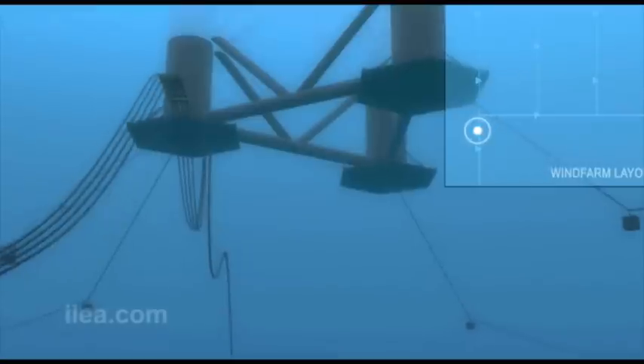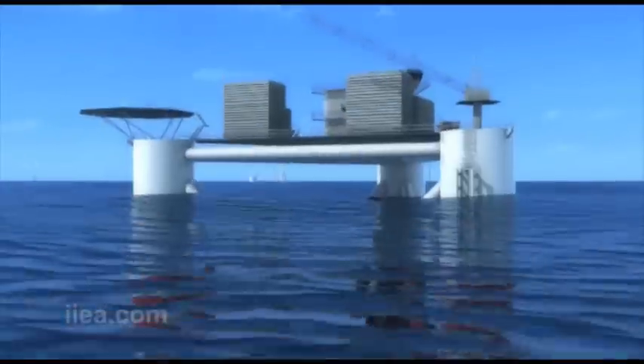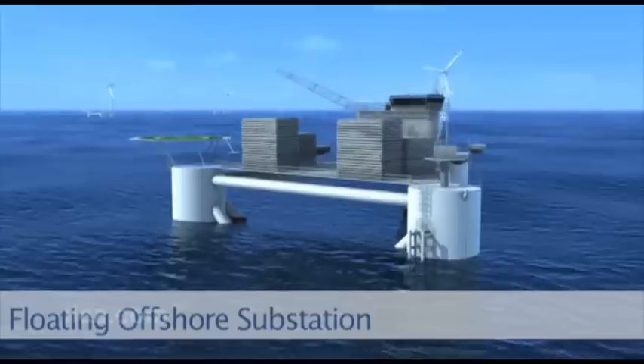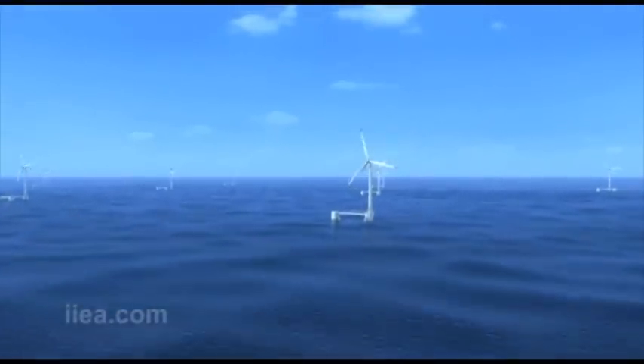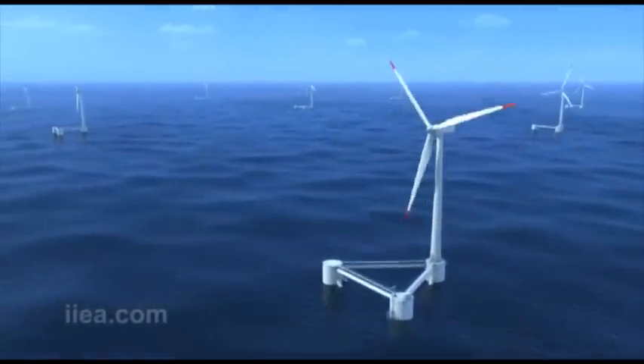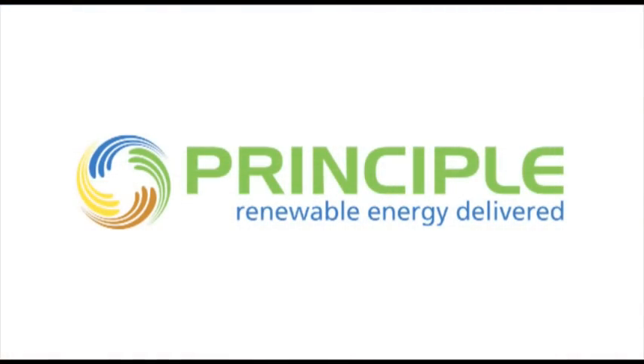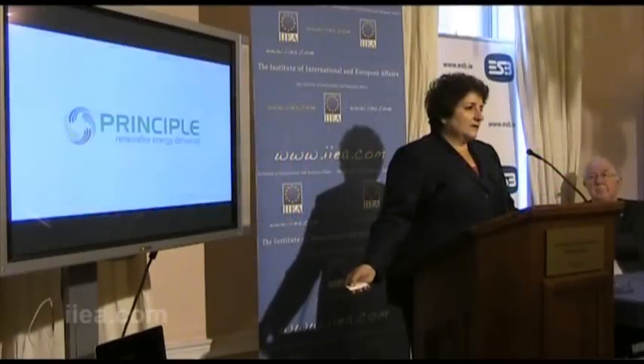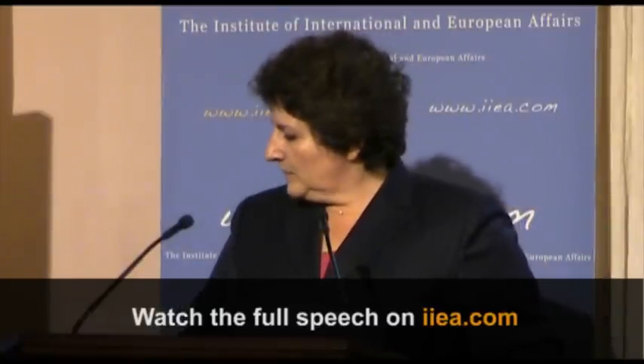Using one of the platforms, you can put all your transformers and gear on one platform and then run only one cable back to shore — that is done in monopile foundations with an offshore substation, and in this case you can use one of the structures. This also gives you an opportunity to provide housing for personnel if necessary, because the structure is very stable. That reduces your travel time to the farm. By being floating and being in deeper water, you can place it offshore so there's no visual pollution — and going beyond 10 miles, beyond the horizon, allows you to eliminate some of those drawbacks as well.